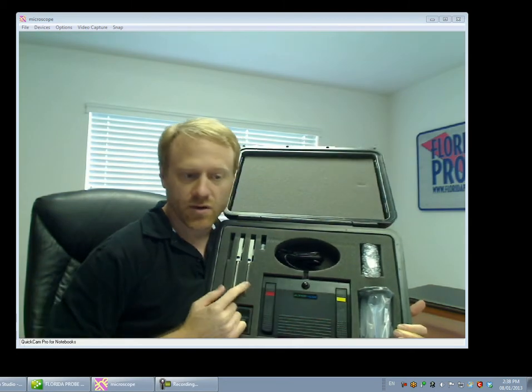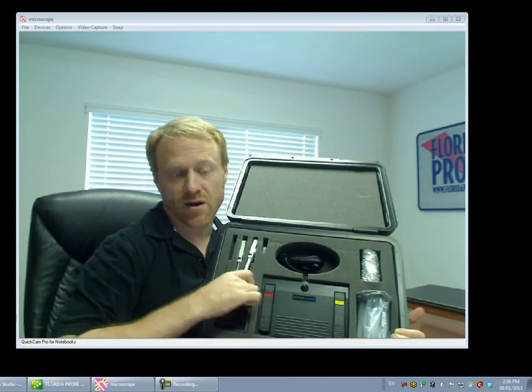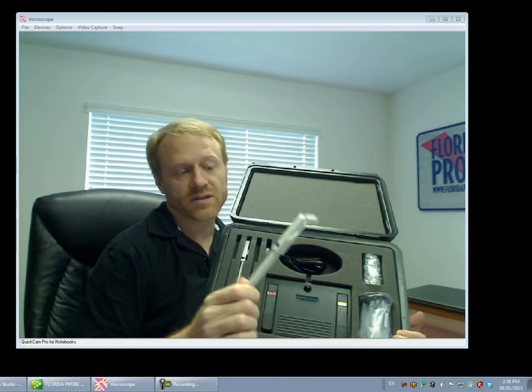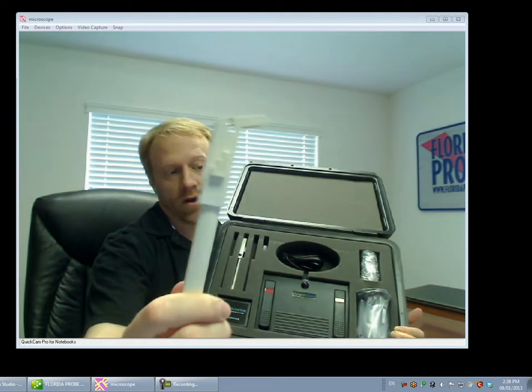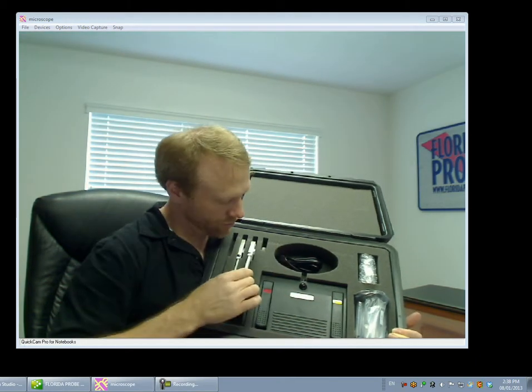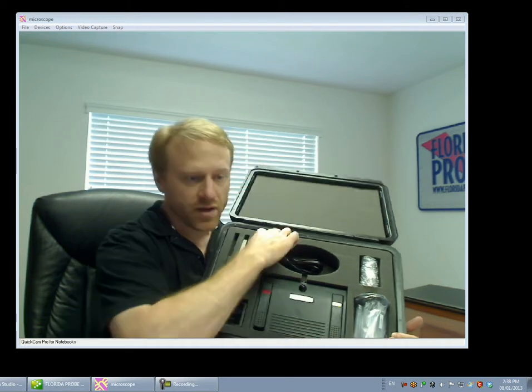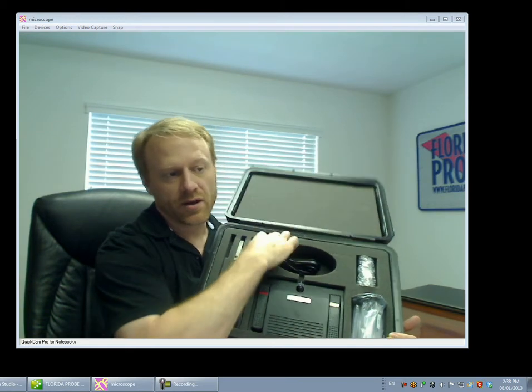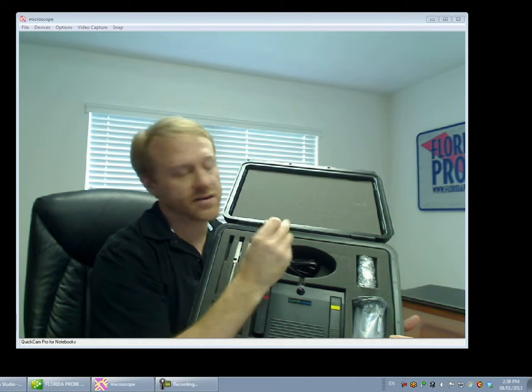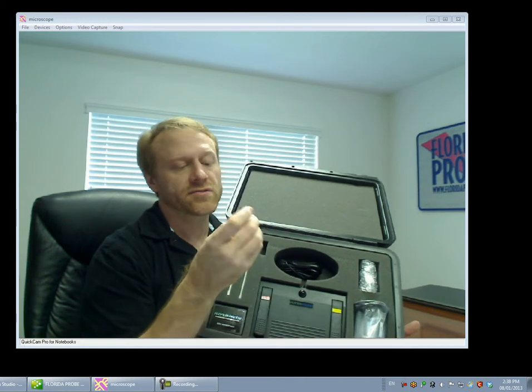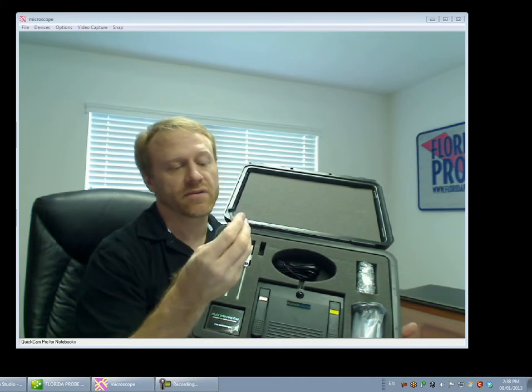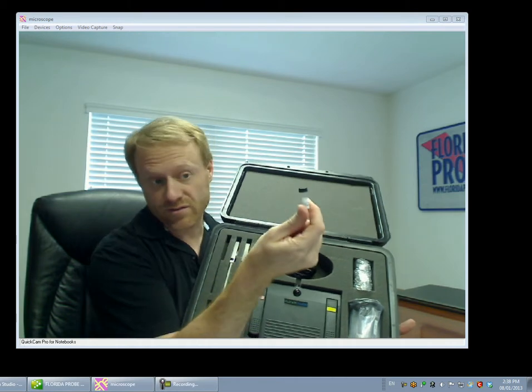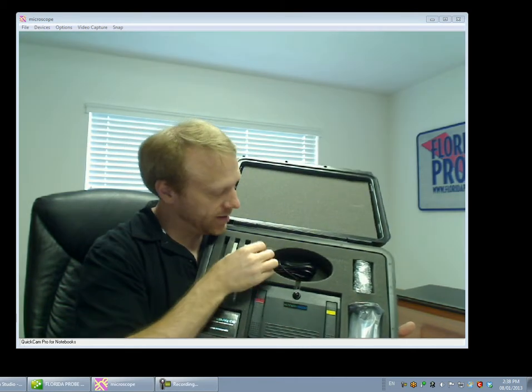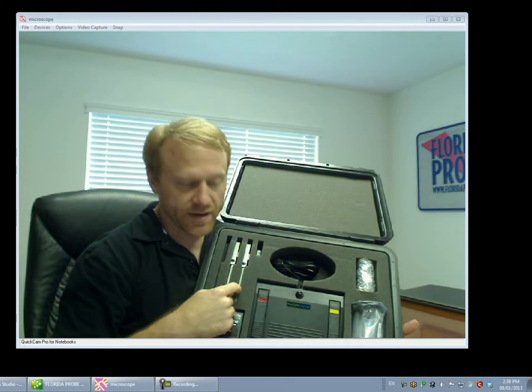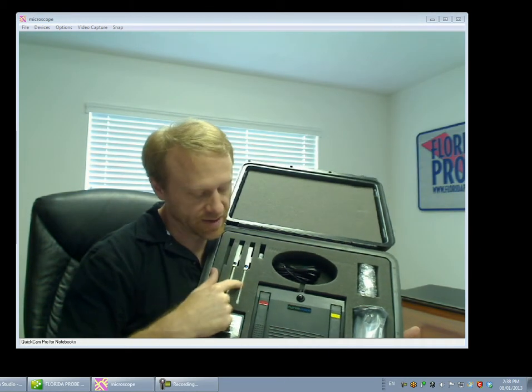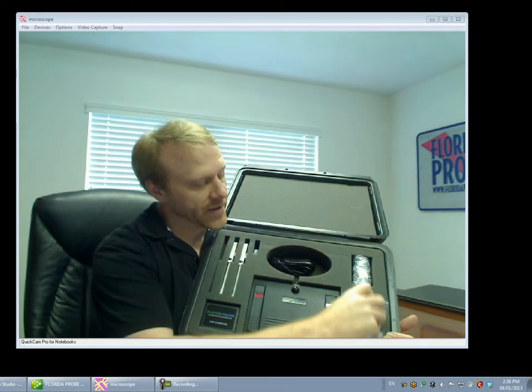You're going to notice that you also have 2 hand pieces. These are steam sterilized, standard autoclave cycle, and have a tip protector on them, so you do have 2 hand pieces per system. You do have extra tips here, so each hand piece already has an implant grade titanium tip in there. These are standard tips designed specifically for the research study, and there are 4 extra tips, or 2 extra tips per handpiece. If you ever bend or drop the handpiece and bend a tip, you'll be able to change those yourself.